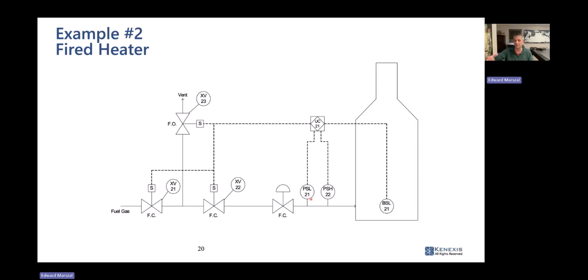find a source of ignition, firebox explosion. For your flame scanner, you can detect things like a slug of nitrogen or carbon dioxide that causes you to lose your flame, even though the pressures didn't change. And then that gas cloud will develop, find a source of ignition, and cause an explosion. So I've got 3 different measurements that are going to ultimately, in the big picture, detect loss of flame and prevent the firebox explosion.